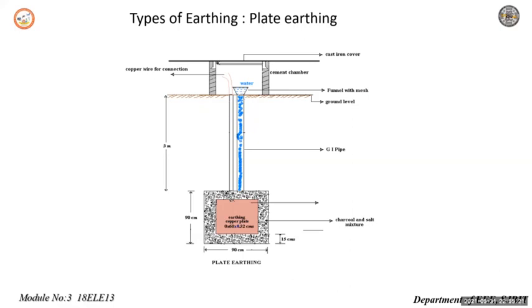The earthing efficiency increases with the increase of the plate area and depth of embedding. If the resistivity of the soil is high, then it is necessary to embed the plate vertically at a greater depth into the ground. The only disadvantage of this method is that the discontinuity of the earth wire from the earthing plate below the earth cannot be observed physically. This may be misleading and may result in heavy losses under fault conditions. The schematic arrangement of plate earthing is shown here. You can see here. This completes plate earthing.